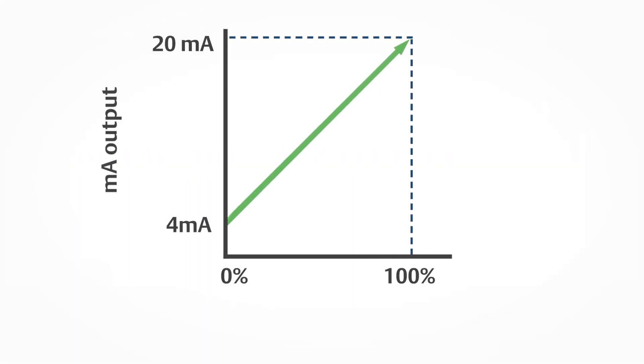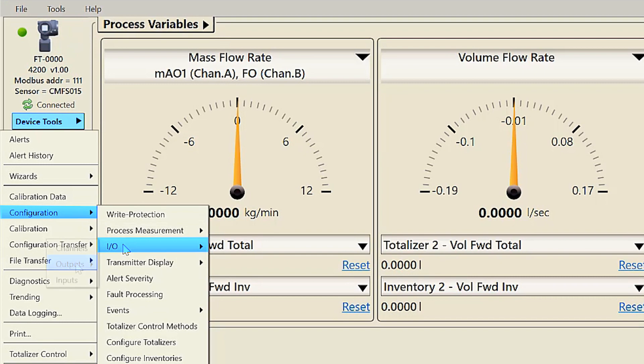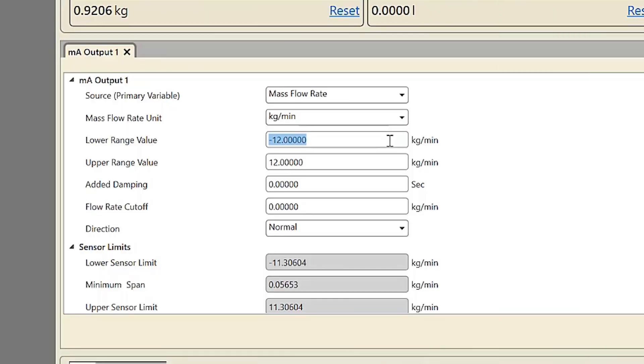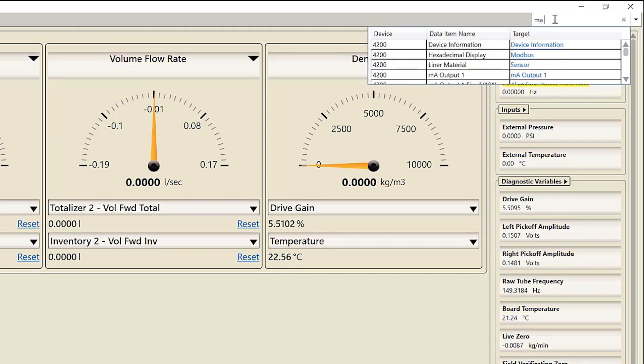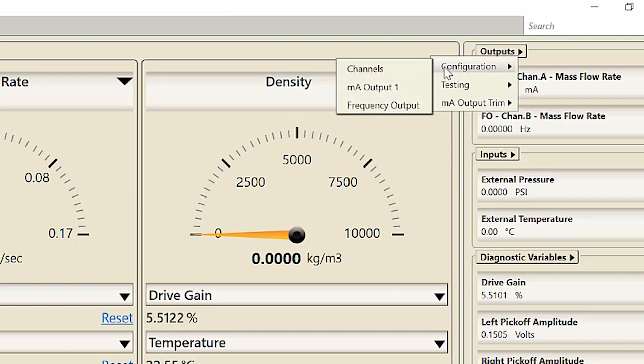The milliamp output represents a process variable in proportion to a signal range of 4 to 20 milliamps. First, configure the milliamp output: using ProLink, select Device Tools > Configuration > IO Outputs > Milliamp Output 1. The milliamp source can be set as mass flow rate, volume rate, temperature, density, or drive gain. Second, configure the range for the milliamp output by selecting the lower range value and upper range value.